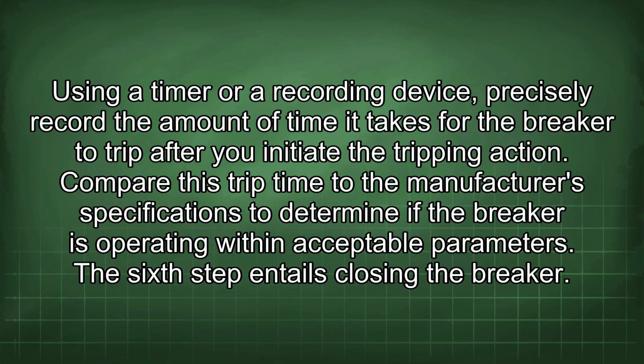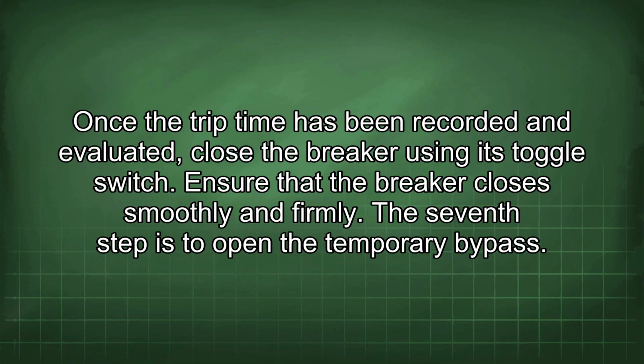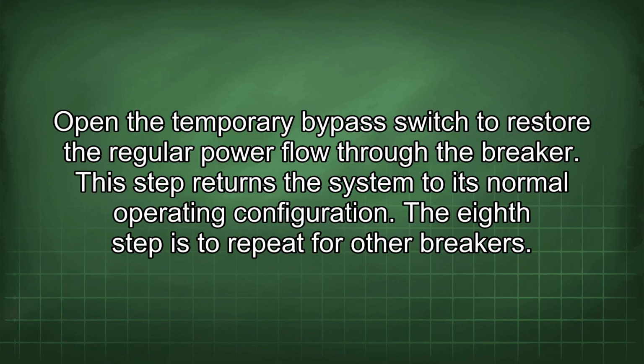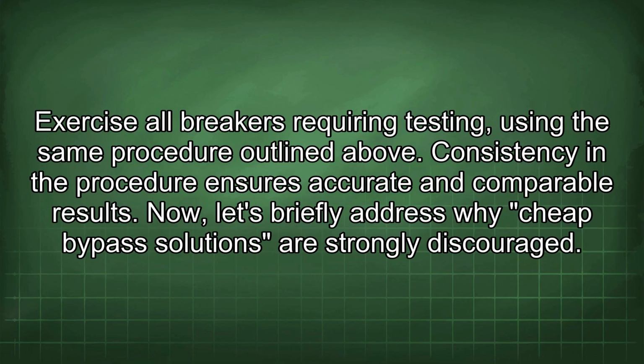The sixth step entails closing the breaker. Once the trip time has been recorded and evaluated, close the breaker using its toggle switch. Ensure that the breaker closes smoothly and firmly. The seventh step is to open the temporary bypass. Open the temporary bypass switch to restore the regular power flow through the breaker. This step returns the system to its normal operating configuration. The eighth step is to repeat for other breakers. Exercise all breakers requiring testing, using the same procedure outlined above. Consistency in the procedure ensures accurate and comparable results.